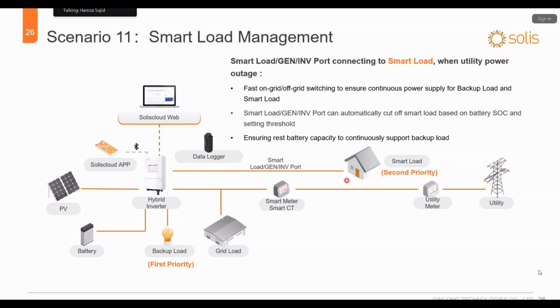Okay. Let's suppose I'm the customer. I have set the 50% SOC to turn off this secondary critical load. So once the battery reaches 50%, it is going to shut down the second priority load. It will help me to save the battery for the backup load.